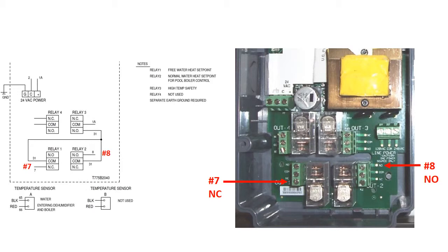Relay 2 controls the pool water boiler. Relay 1 is part of the air cooling mode. When the air temperature is satisfied but additional dehumidification is required, an extra degree of free heat will be added to the pool water before the heat is discharged outdoors.